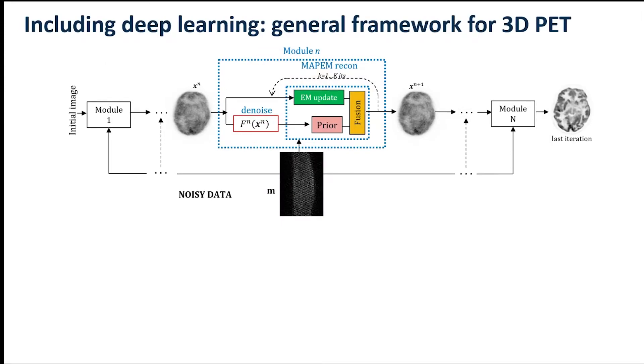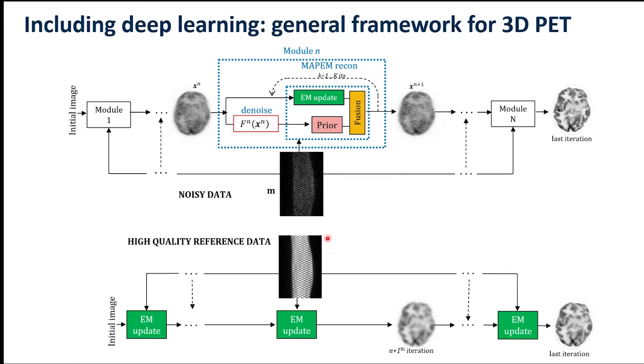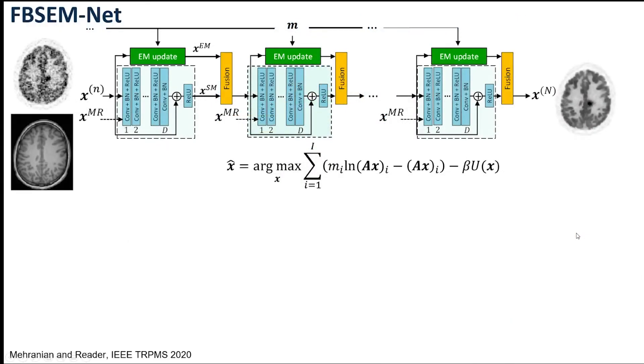I'm showing here a representation of about three methods in the PET literature, which can be represented in a construct where we take our current update and learn a network to denoise it, providing a fixed image prior for use in a MAP-EM update — just like the intermediate smoothed image in the previous MAP-EM updates. We can now find that intermediate image from a deep network and iterate that to get a new update. To train up that network, we need high-quality reference data, so we use a much higher count version of the scan data, needing low-count/high-count pairs, trained with a mean square error loss function.